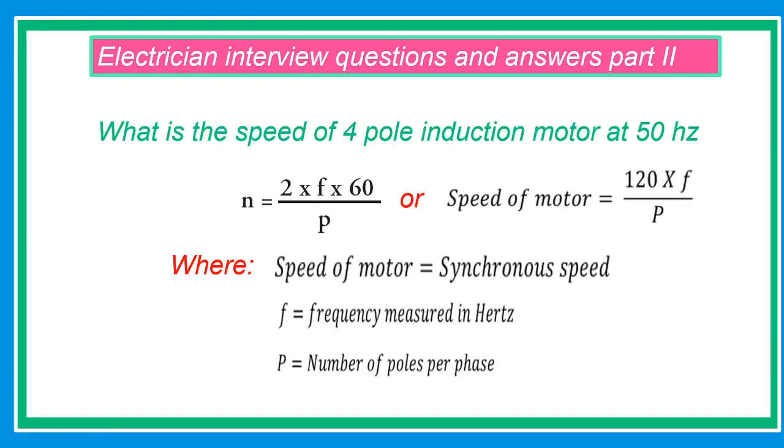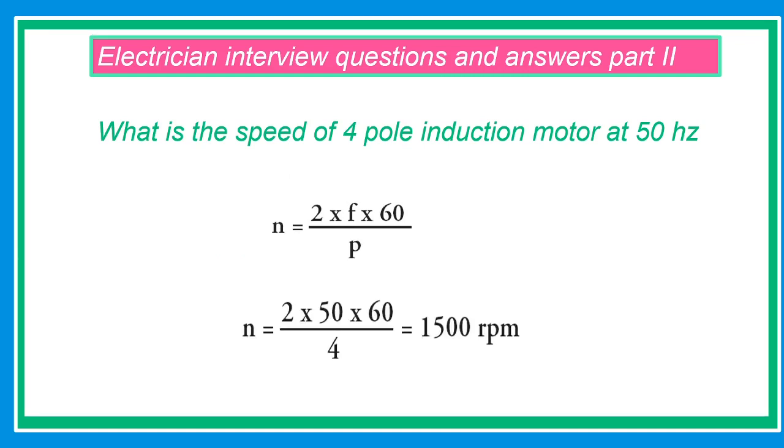What is the speed of a 4-pole induction motor at 50 hertz? The formula is n equals 2 times F times 60 over P, or 120 times F over P, where speed of motor is synchronous speed, F equals frequency measured in hertz, P is the number of poles per phase. The answer is n equals 2 times 50 times 60 over 4 equals 1,500 rpm, or revolutions per minute.